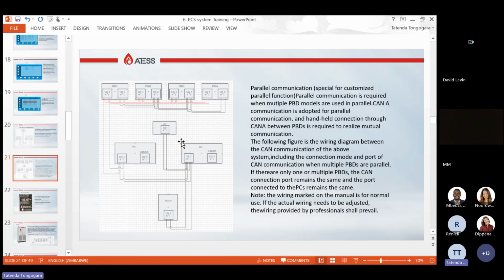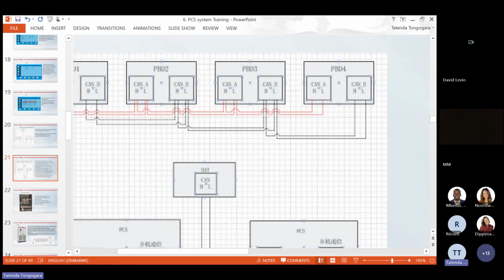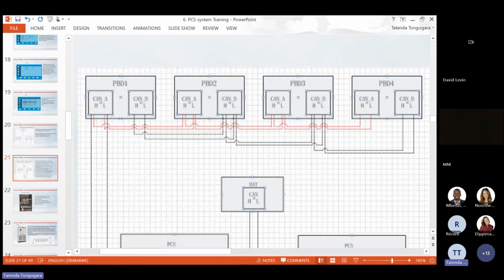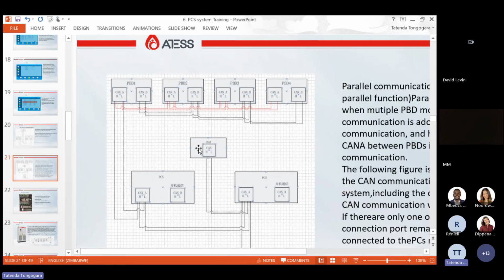So this is the full communication diagram for our PBDs. In this case, we have 4 PBDs. If you check here, the red dotted lines are our CAN A, and we also have CAN B that's being paralleled. Our CAN A is coming from the PCS. From the battery, you go to PCS 1, it's paralleled to PCS 2, and then from PCS 2 we parallel with PBD number 1 in a daisy chain, on the CAN A ports. And then the same for the RS485 interface.